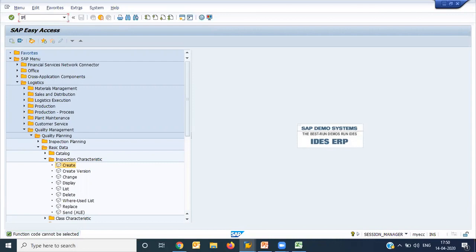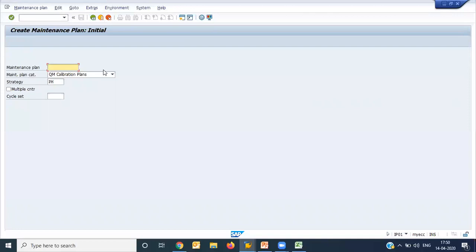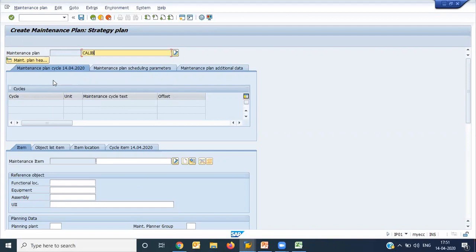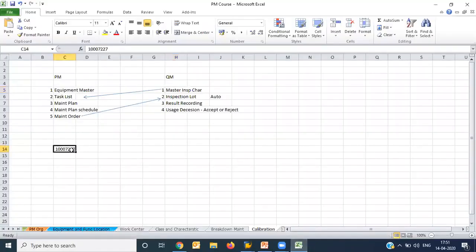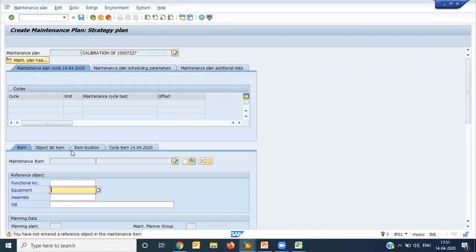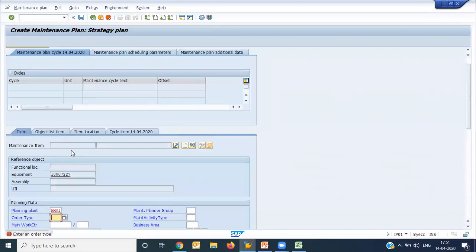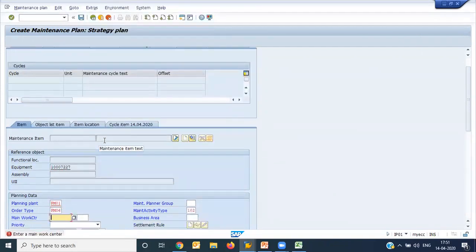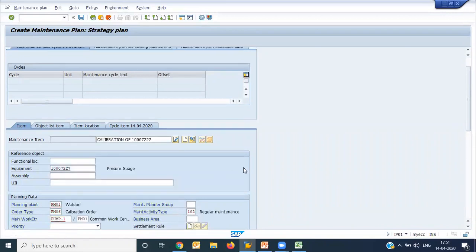I saved the task list as number 87. Now let us go and create a maintenance plan, since that is the primary requirement. We can create a separate maintenance plan category for calibration. I am giving the description 'Calibration.' The maintenance plan creation remains the same except for one thing: here we must use a calibration order type — such as PM04 — because a calibration order must be assigned to the inspection type.